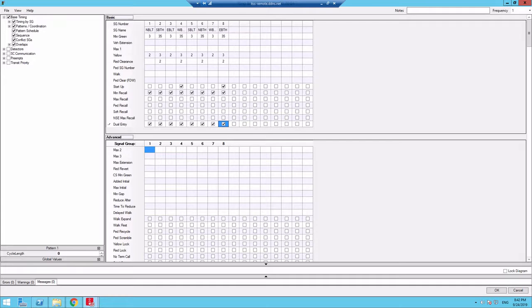So that's minimum recall. Maximum recall is when the detector detects a lot of demand. When there are so many vehicles that the controller has to do a continuous call for vehicle service on the phase, this means that it will present the green through signal at the maximum amount of time allowed. So because I don't actually designate a max for the signal timing, you can't really choose the difference between min and max recall.